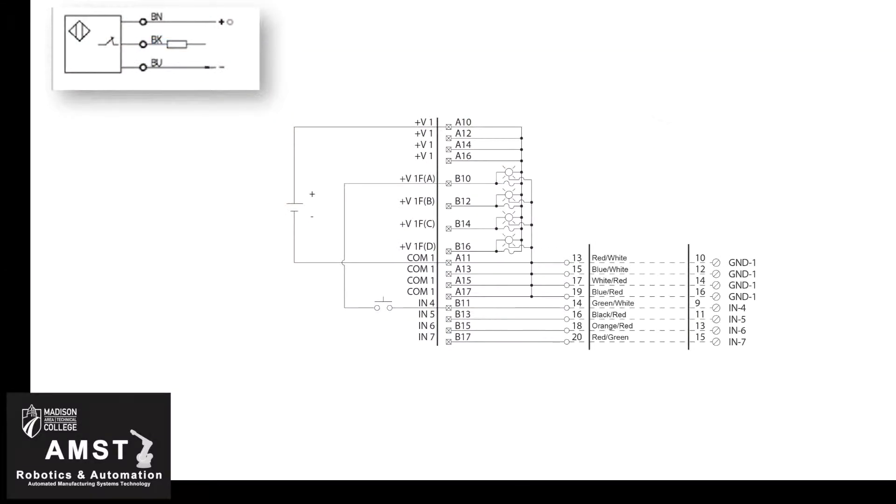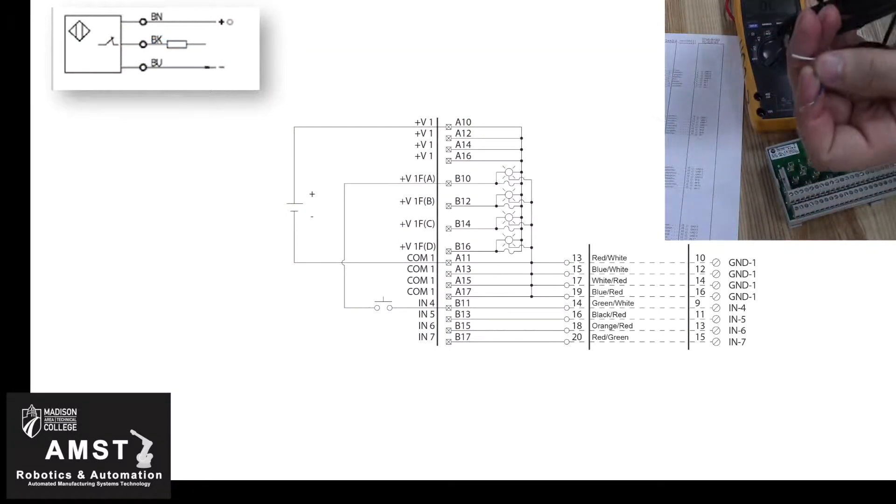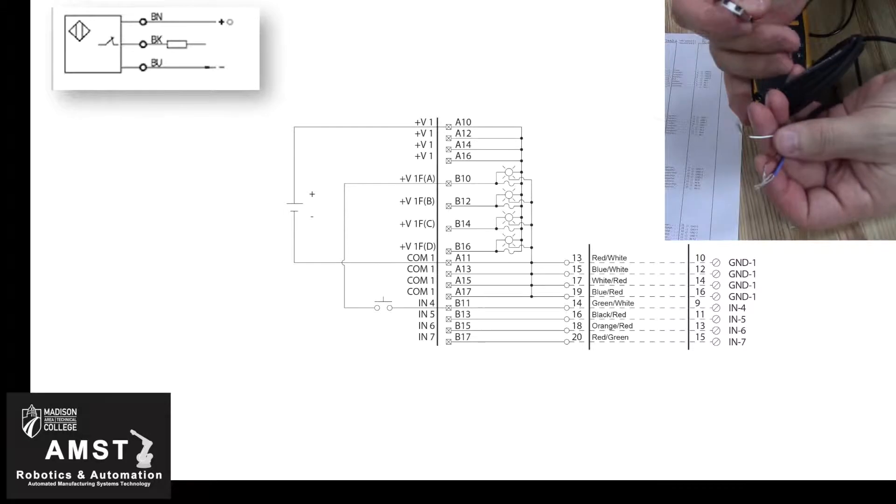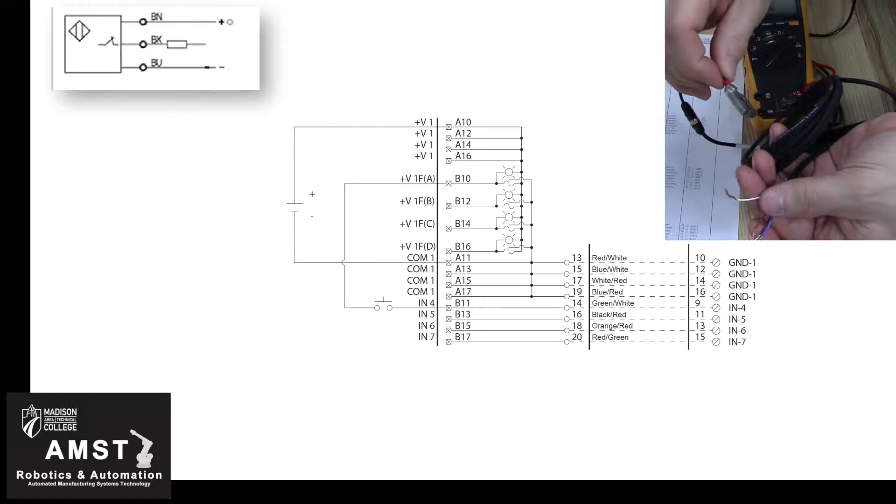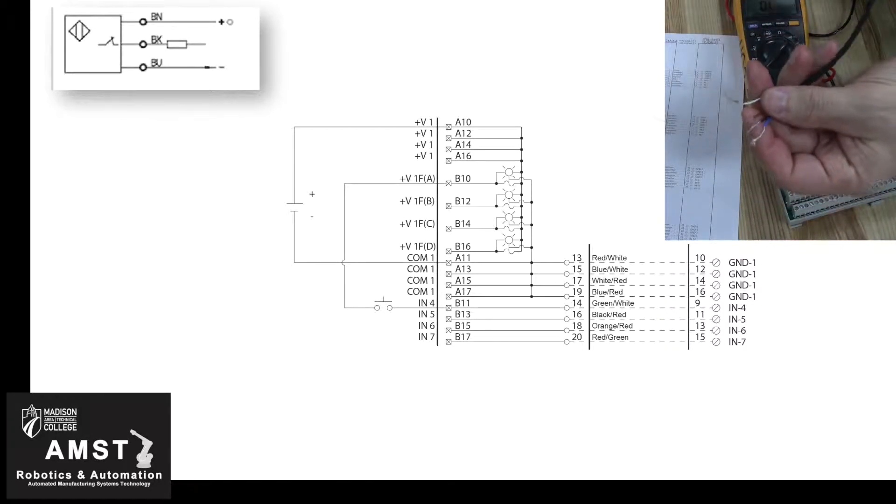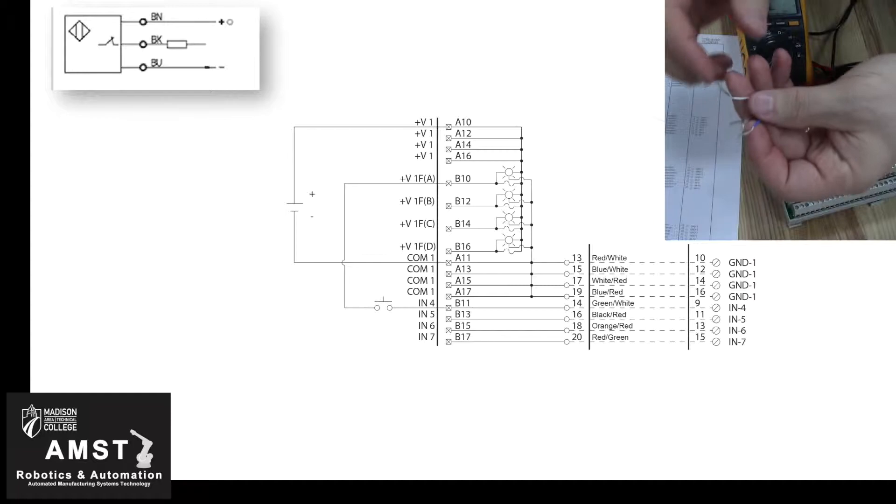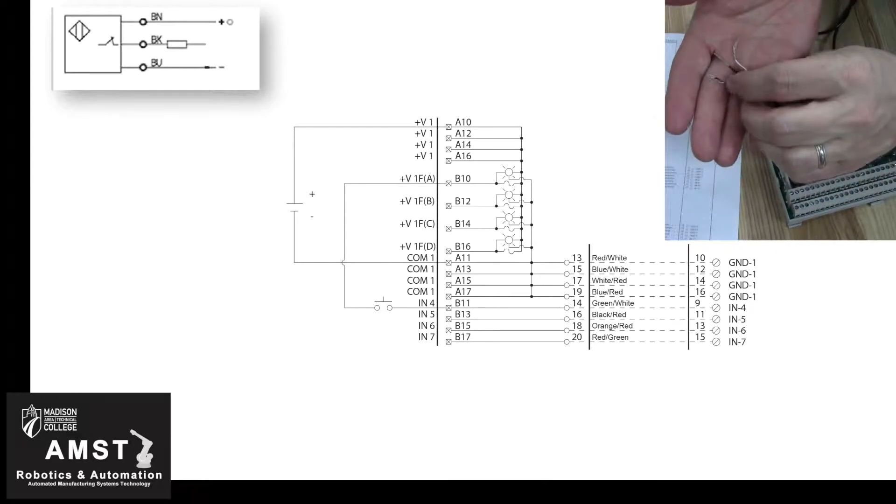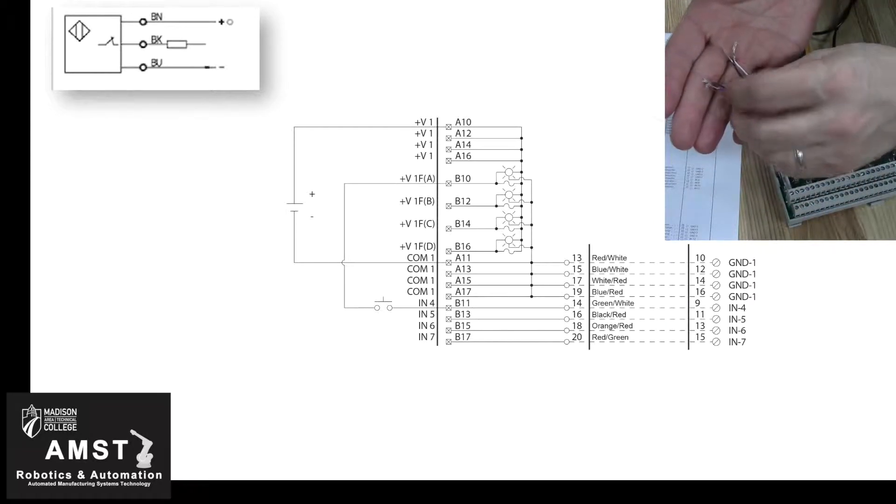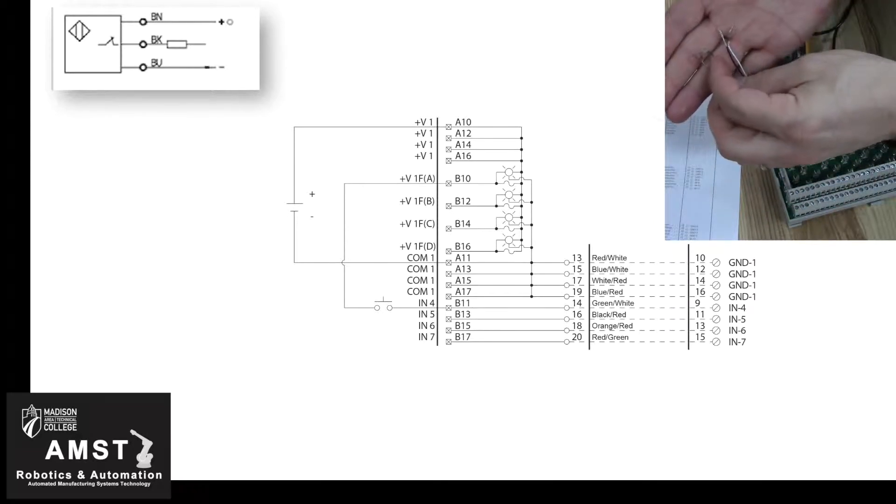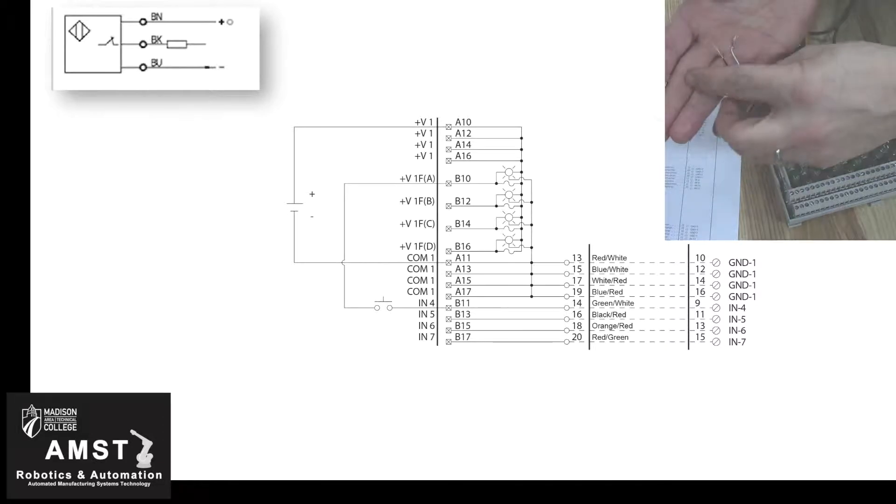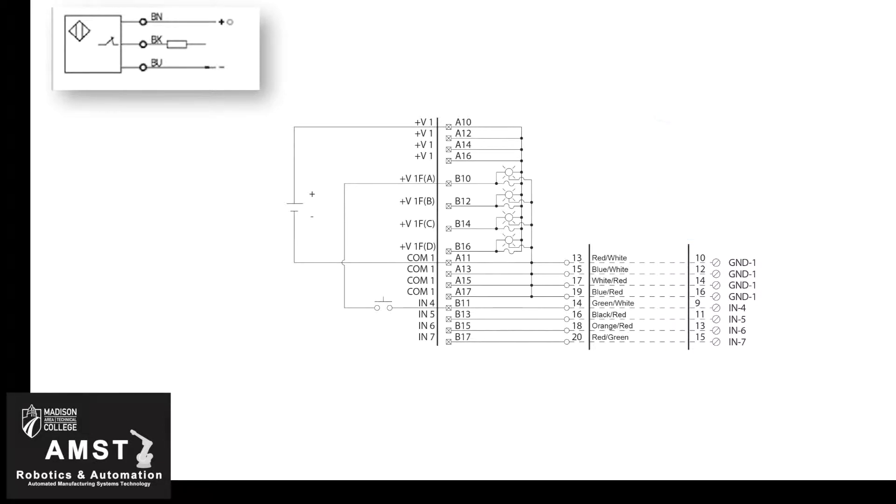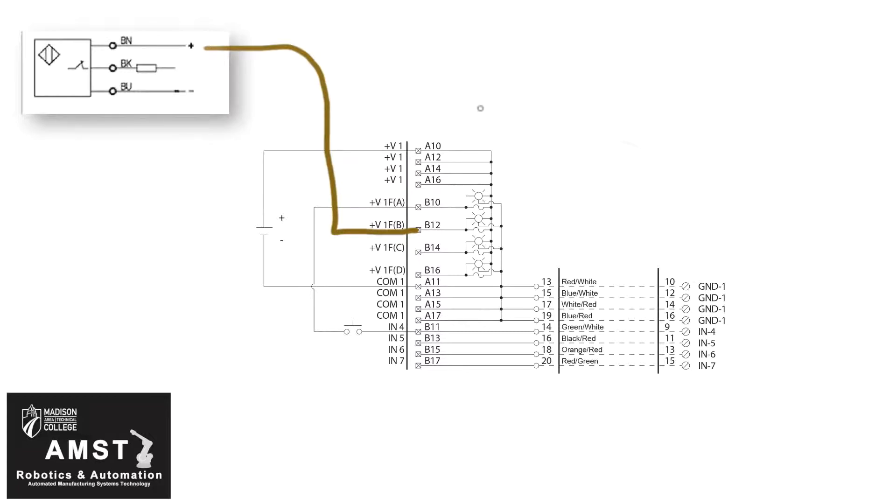Now let's talk about wiring up a three-wire sensor like this PhotoEye. The Keyence sensor has a brown positive line, a black signal line, and a blue negative connection. The white is a normally closed, which we won't deal with for now. Let's start with the brown wire, which is going to get connected to the B12 terminal. That'll supply 24 volts fused to our field device.